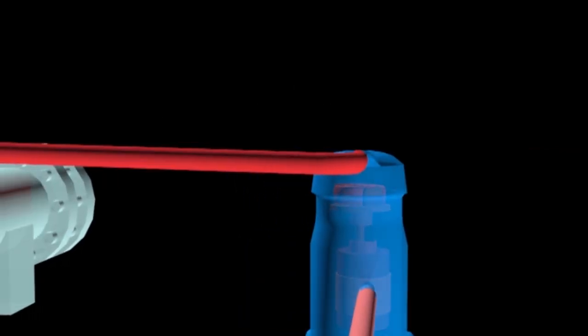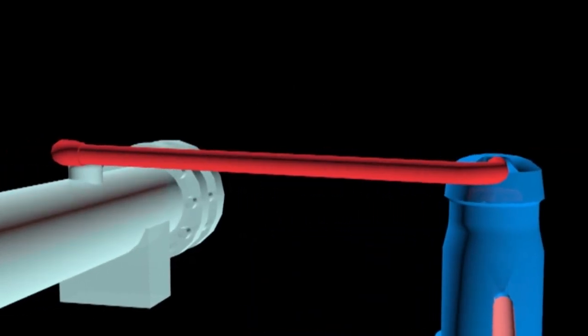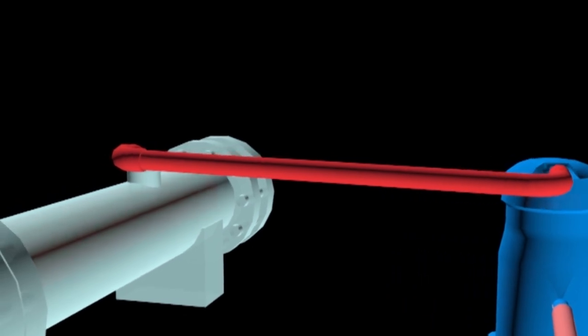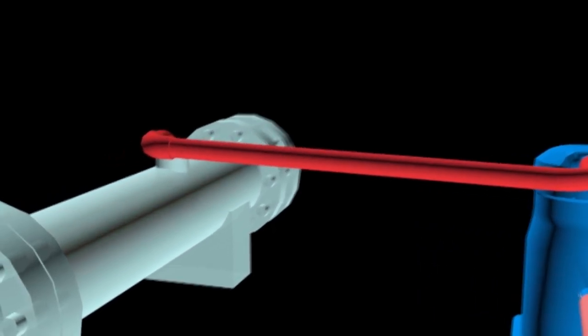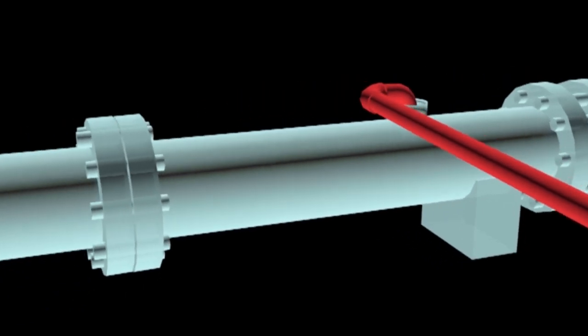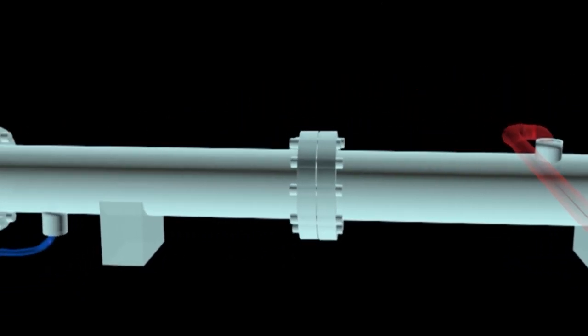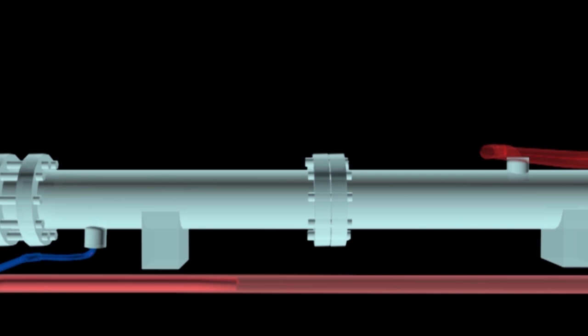Condenser. The refrigerant as a high-pressure gas will enter the condenser at a temperature higher than the temperature of the condenser water. In the condenser, the heat will be eliminated to the condenser water from the cooling tower through the process of convection and conduction.